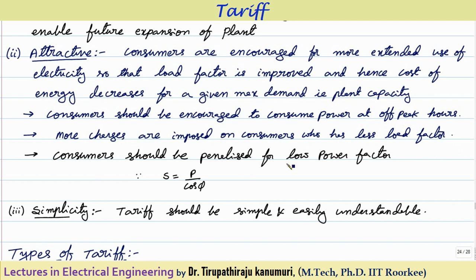The consumer should be penalized for low power factor. We know that apparent power equals active power divided by cos phi. Active power is the actual power doing your work. For a given active power, as the power factor decreases, apparent power increases. The rating of the power plant and all equipment mainly depends on apparent power. As the power factor decreases, the apparent power increases — meaning more rating is required, or for a given rating, we cannot supply the required value of power. That is why the consumer should be penalized if the power factor is low. To understand this concept clearly, you can refer to the power factor improvement topic where these things are discussed in detail.